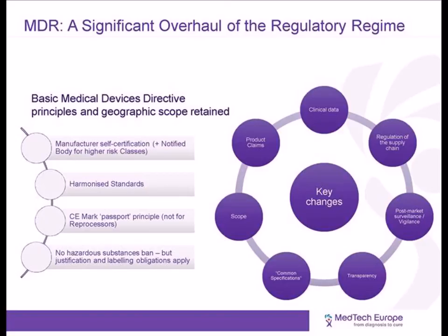In addition, manufacturers' pre-market clinical evidence obligations are set to increase quite significantly. The opportunity to CE mark devices according to the so-called equivalence or literature review route is reduced. This, combined with an explicit requirement for many high-risk devices to undergo pre-market clinical investigations, means there is an overall expectation to generate fresh pre-market clinical data.